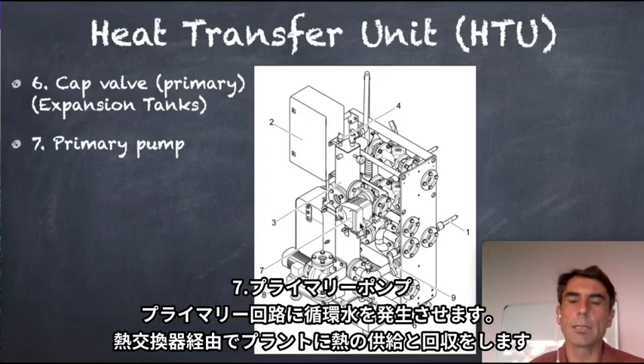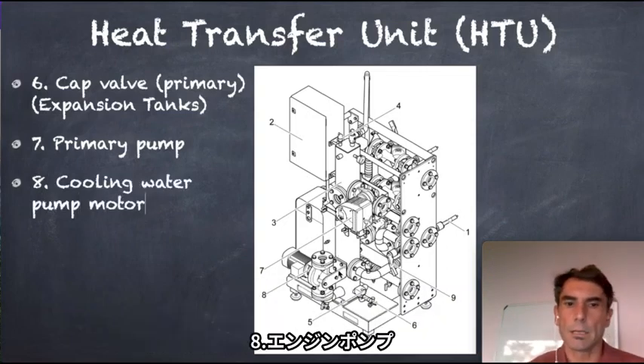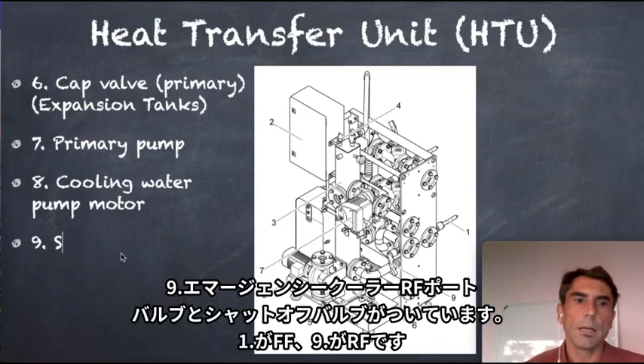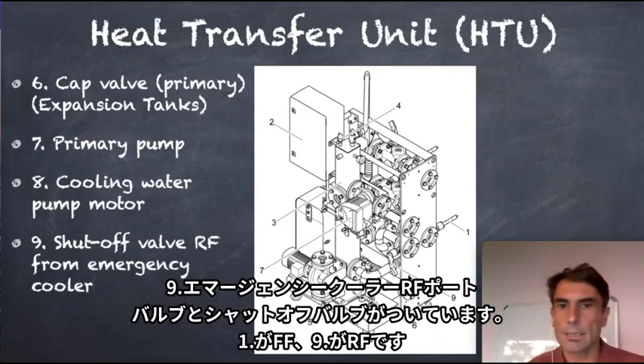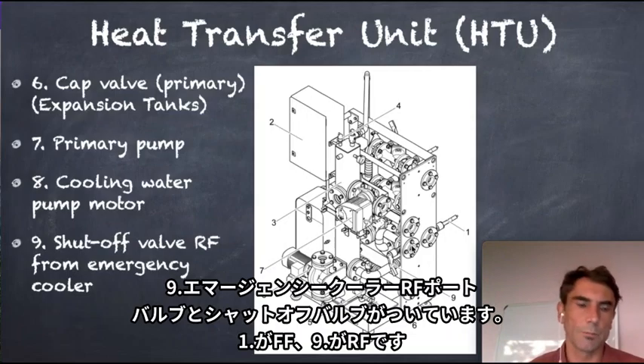Number 7, here is the primary pump. The primary pump is the pump for the primary circle to supply the heat to the plate heat exchanger and the client or plant. Number 8 is the engine pump, so the cooling water pump. Then we have number 9. It's on the other side, the return flow connector flange with a shut-off valve for the emergency cooler. So the forward flow is here, number 1, and number 9 is the return flow from the emergency cooler radiator.